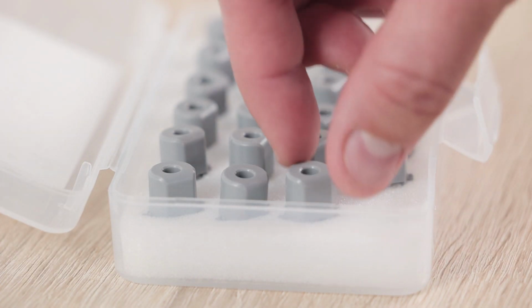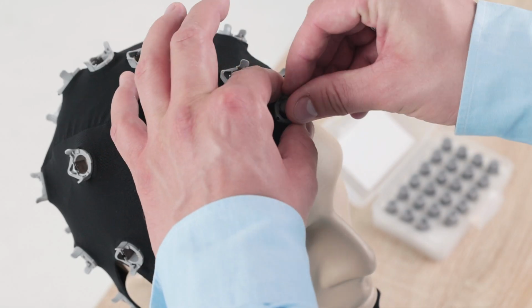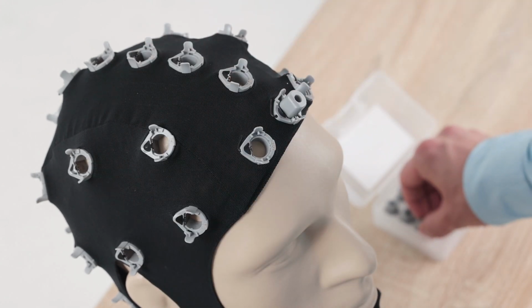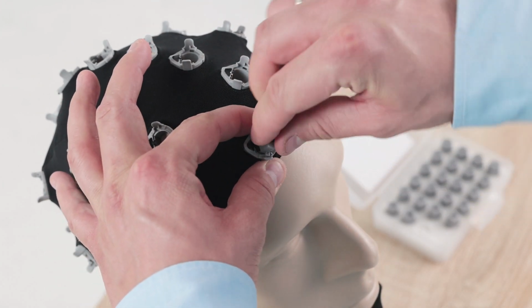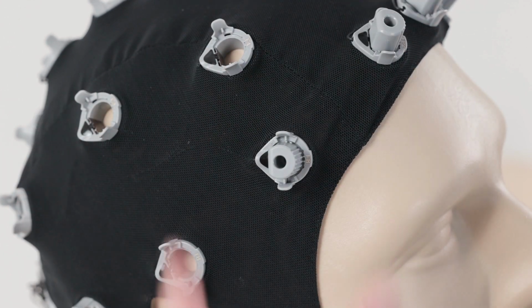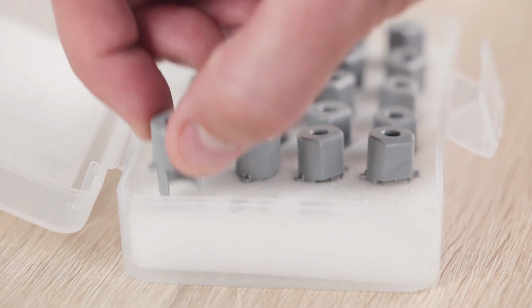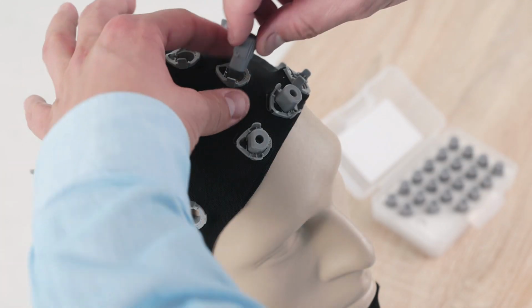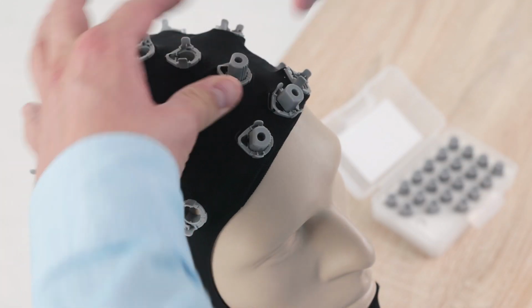We will first show a faster approach where the sponges are placed in the cap before it is mounted on the subject. Insert the sponge holder into the electrode base. Screw the sponge holder clockwise. A click sound indicates that the holder has been properly placed in the electrode base.